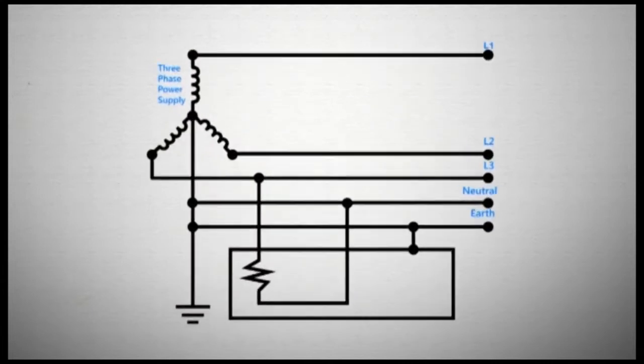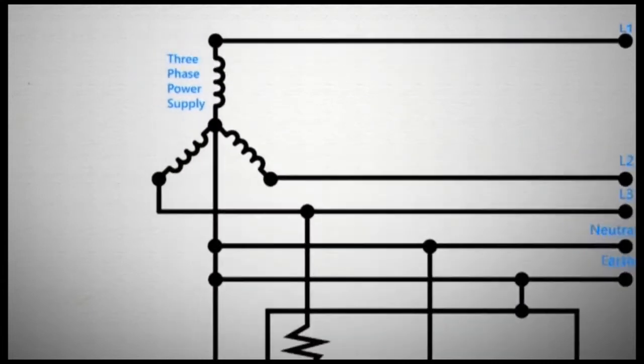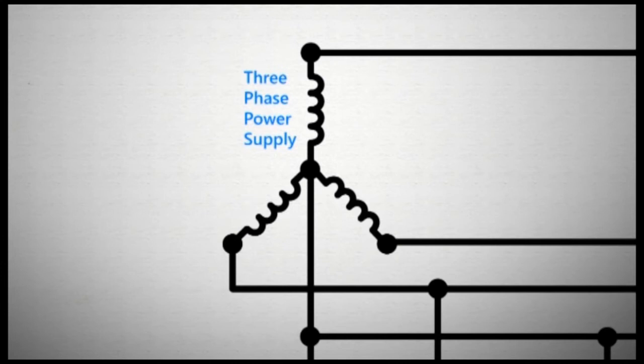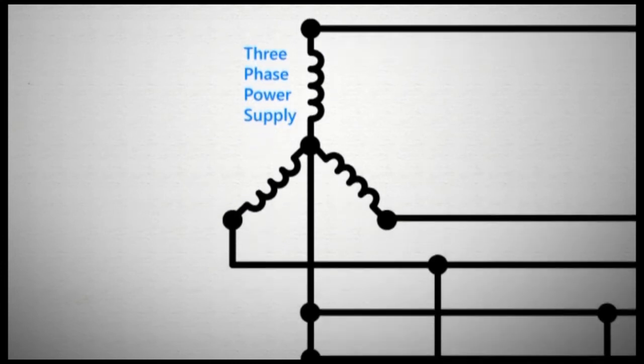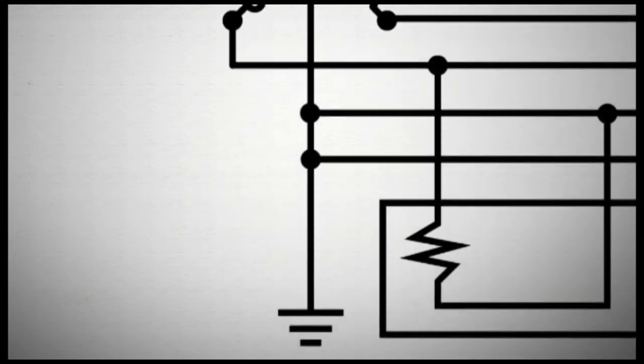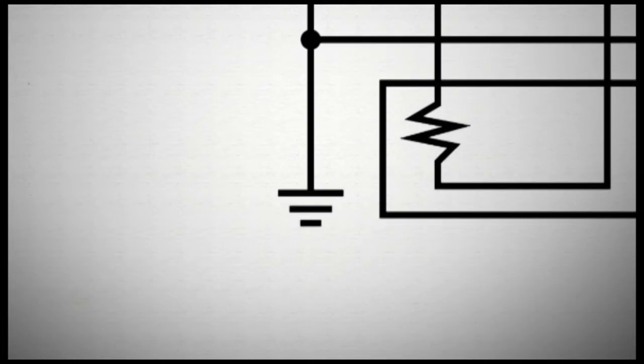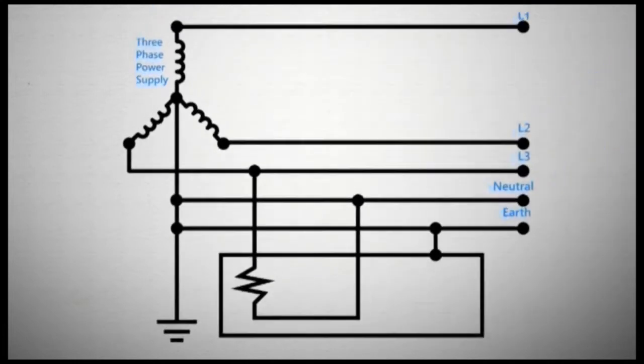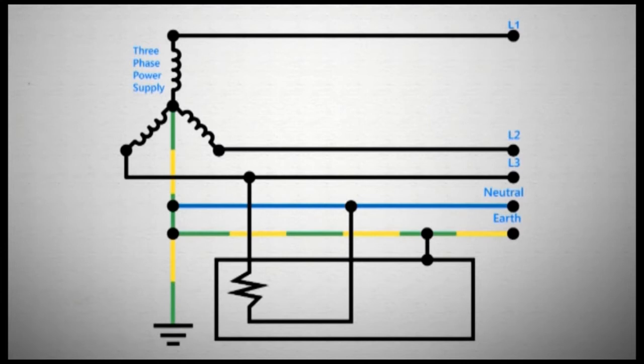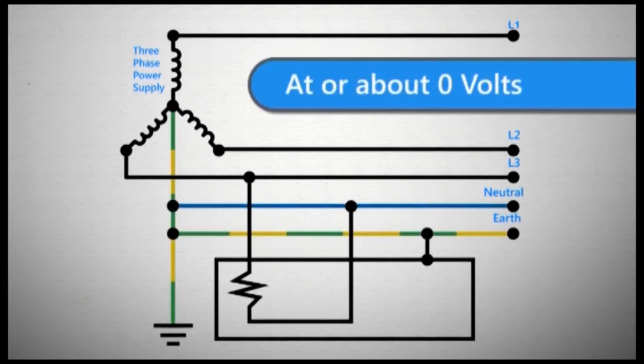A second technique used for compliance with Regulation 8 is connection to a common voltage reference point. In electricity systems, it is standard practice to connect transformer neutrals to the general mass of Earth. Therefore, provided this earth connection is electrically and mechanically sound, the earth and neutral conductors in a system should be at earth potential, in practical terms, at or about 0 volts.